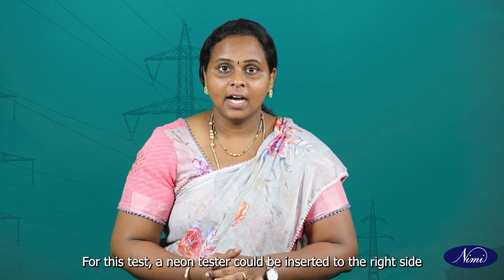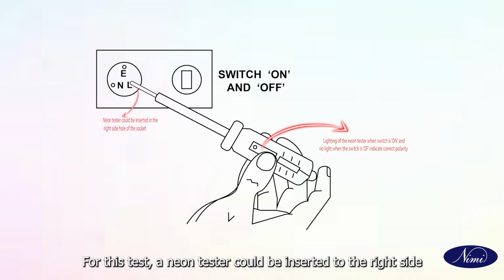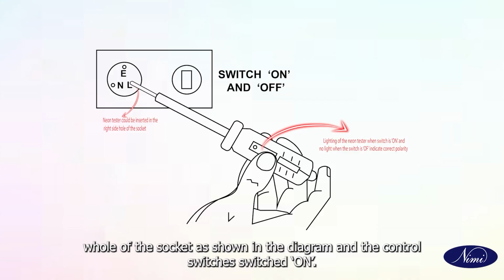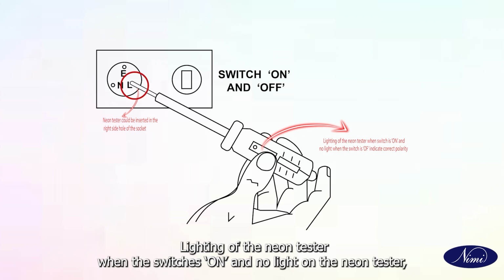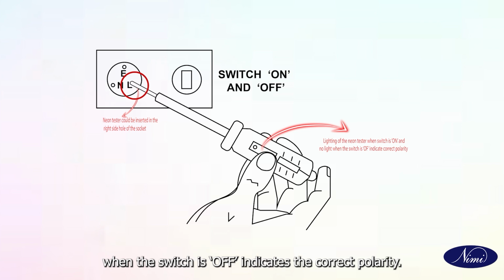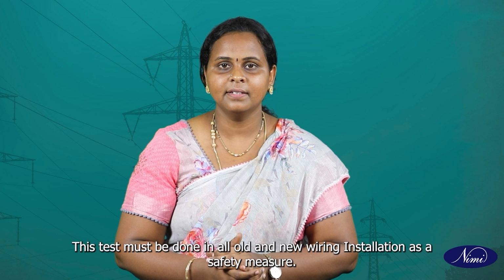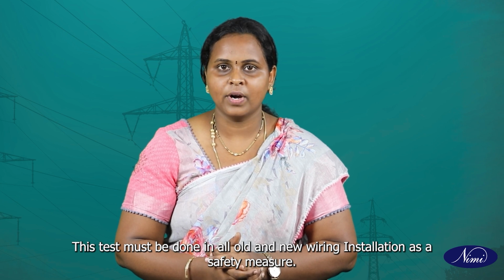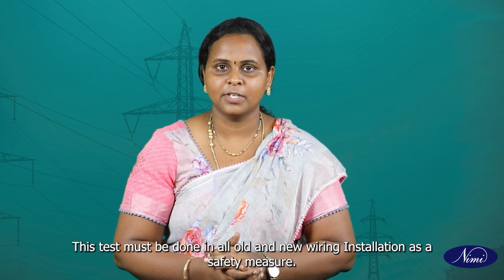For this test, a neon tester could be inserted into the right side hole of the socket as shown in the diagram, and the control switch is switched on. Lighting of the neon tester when the switch is on, and no light on the neon tester when the switch is off, indicates the correct polarity. This test must be done in all old and new wiring installations as a safety measure.